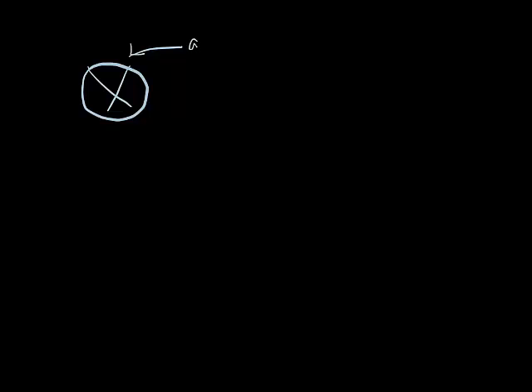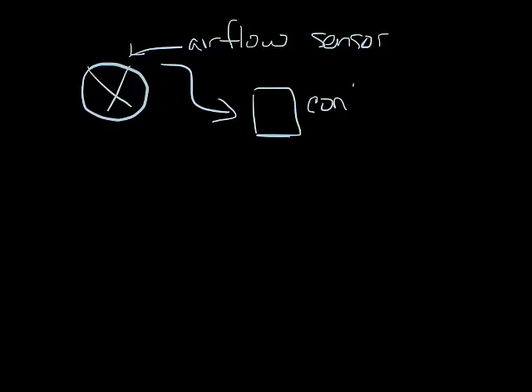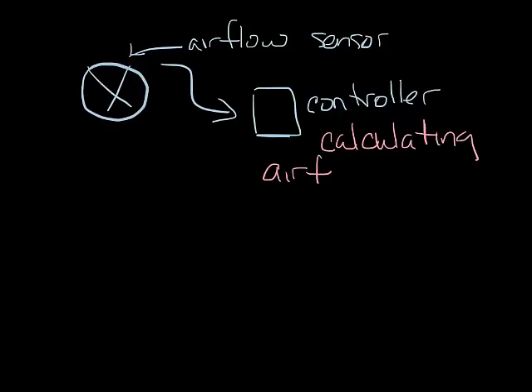Now let's look at pressure independence. In a pressure independent VAV box, the airflow volume is independent of the changes in pressure. Pressure independent VAV boxes have flow sensors that measure the pressure in the box and send this information to a controller. Using the equations we covered in the last podcast on pressure basics, the controller can calculate the airflow and control the damper to adjust for changes in pressure in the system.